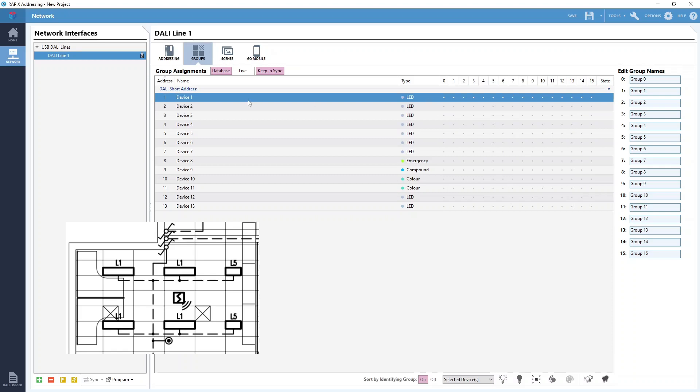So if we are going to use DALI group 1 for our room and we want to start by adding the DALI device at short address 1 to the group, all we have to do is click the little grey dot here that corresponds to the fitting we want and the group we want it in. The grey dot means the device isn't in that DALI group, but once it's added to the group the dot will change into the number of the group to show that it is now a member.